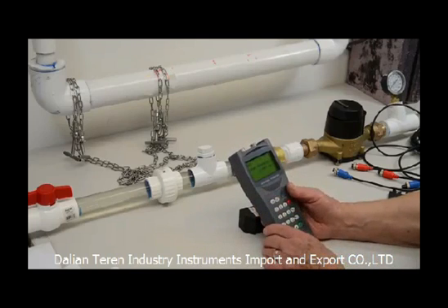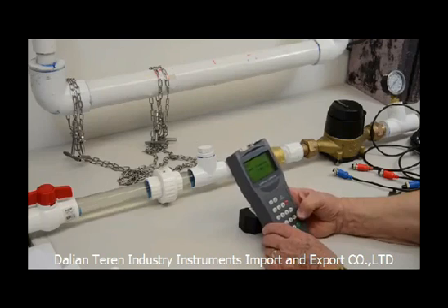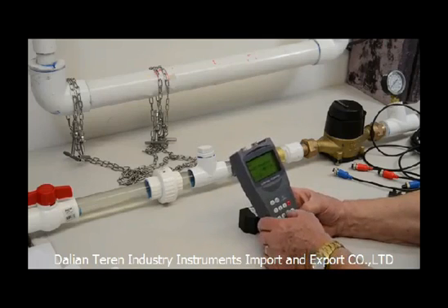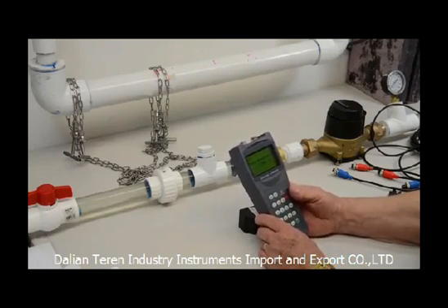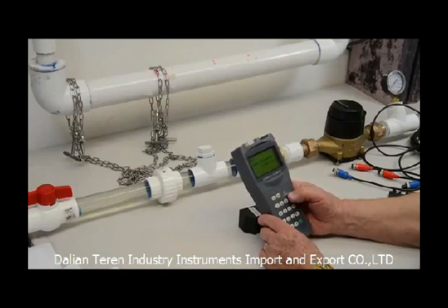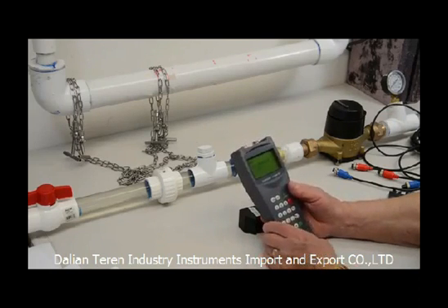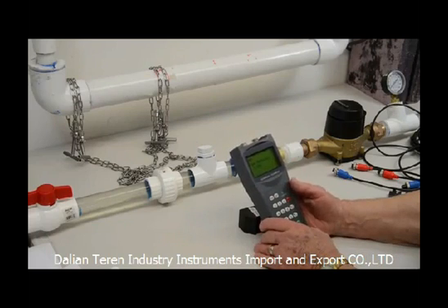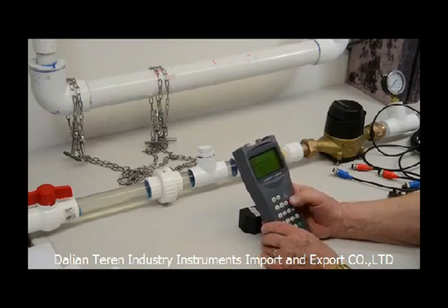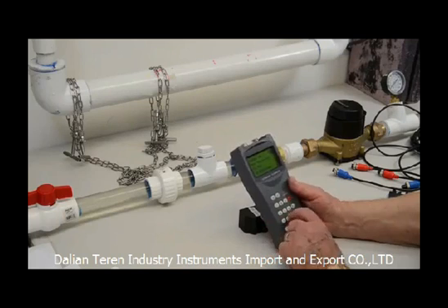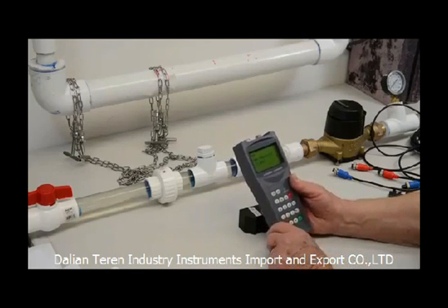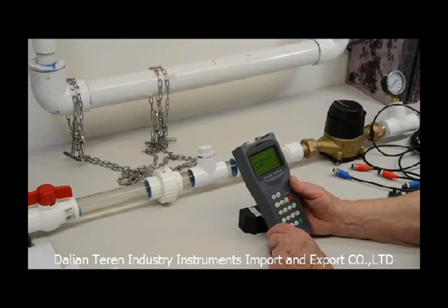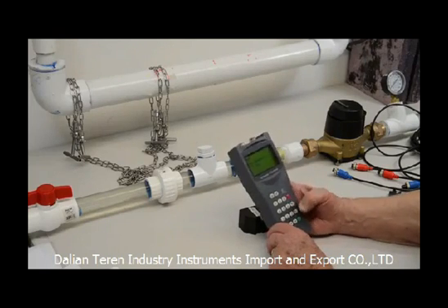The next thing I'm going to do is push M13, which gives me my inner diameter. So I push enter, and my inner diameter in this case is 2.067. 2.067, enter. Okay, so now I've got my inner diameter. The next thing I want is the pipe type, so I'm going to push menu 1-4, and I have an option here of the different kinds of pipe. In this case, I'm using PVC, so enter. The next thing I'm going to do is to push M20, and that tells me the water or whatever my flow through the pipe is going to be.